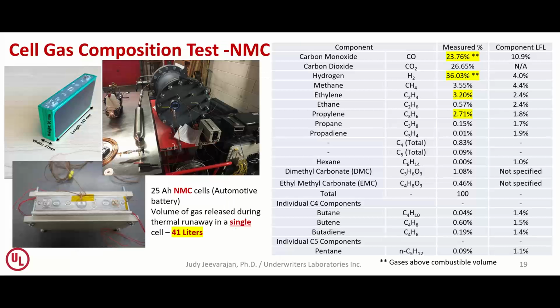Here I have some information on the gas composition very quickly on the cell level. The NMC cell, as I said, is a 25 amp hour cell, and a single cell released about 41 liters of gas. You can see on the right side the components: the carbon monoxide was higher, and much higher than the lower flammability limit, and hydrogen was also high in this case. But what we have here is a lot of carbon dioxide and carbon monoxide, almost in the same ratio.